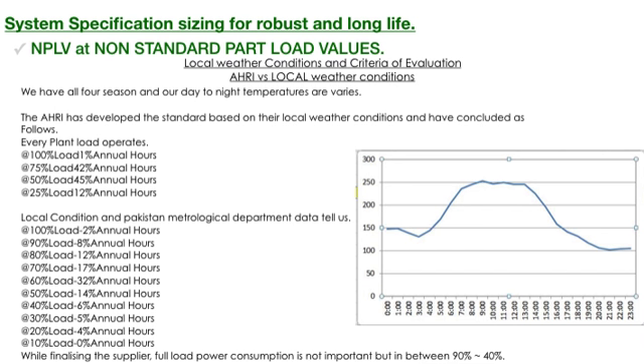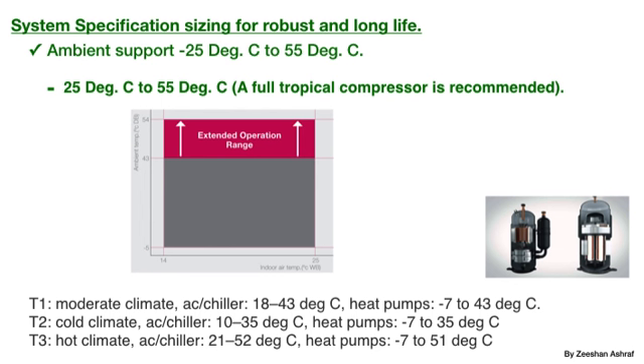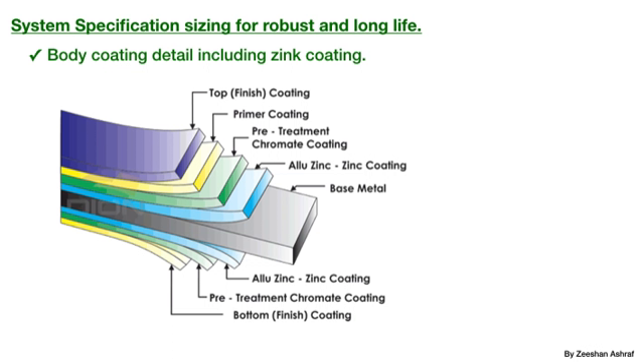So when you buy any AC equipment, you must remember part load performance is important. T3 ambient compliant compressor is the more robust type of compressor, as it supports ambient temperatures up to 52 degrees Celsius. Otherwise the AC body gets corrosion and is completely damaged in 5 years. Compare the specification of VRF outdoor unit with split.